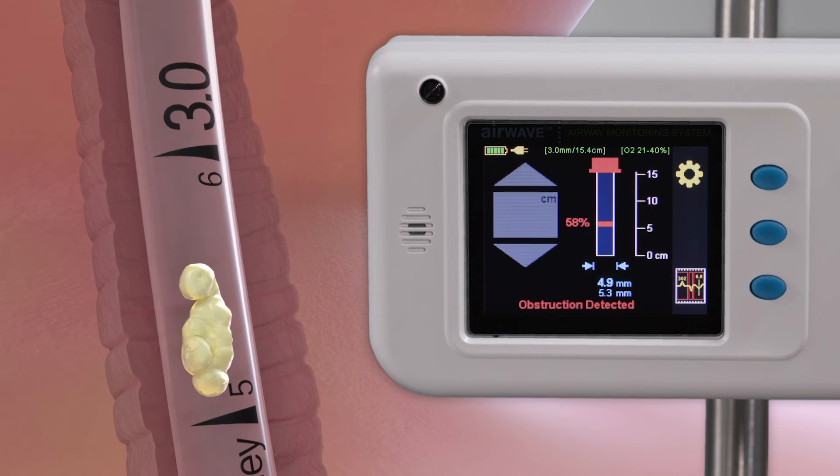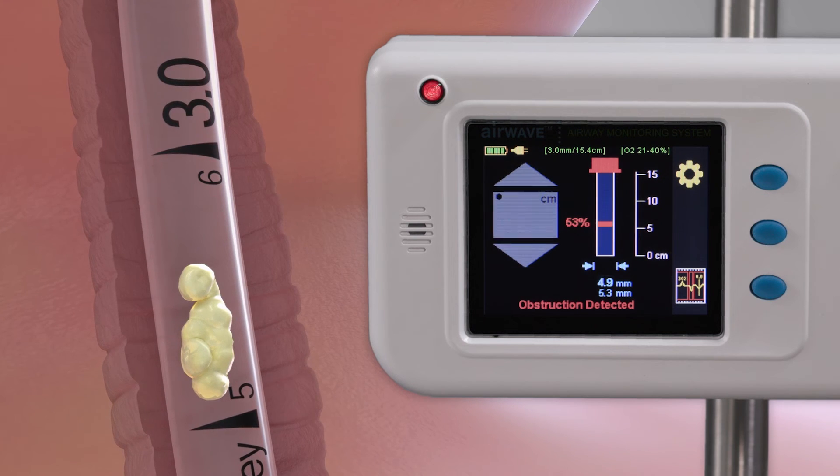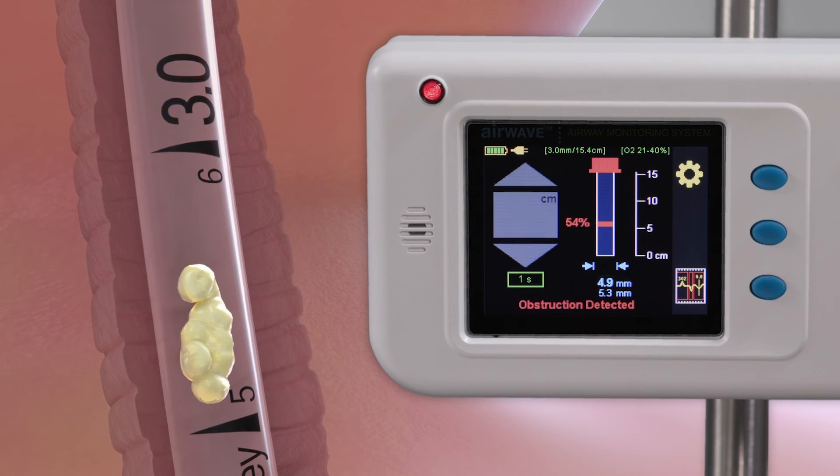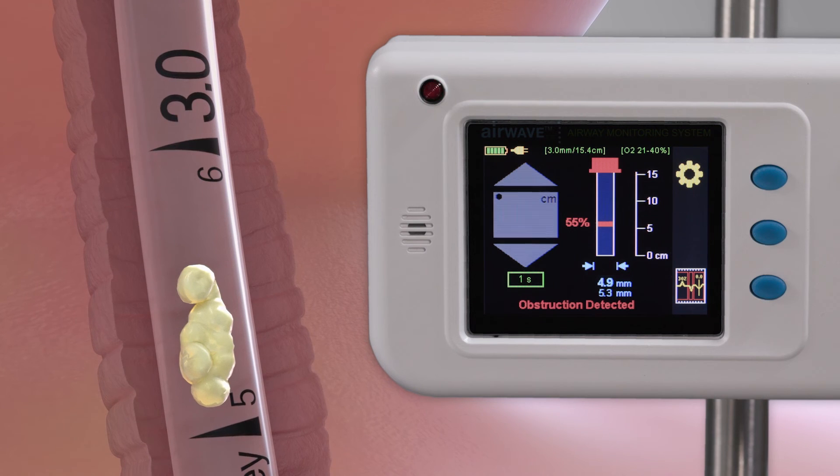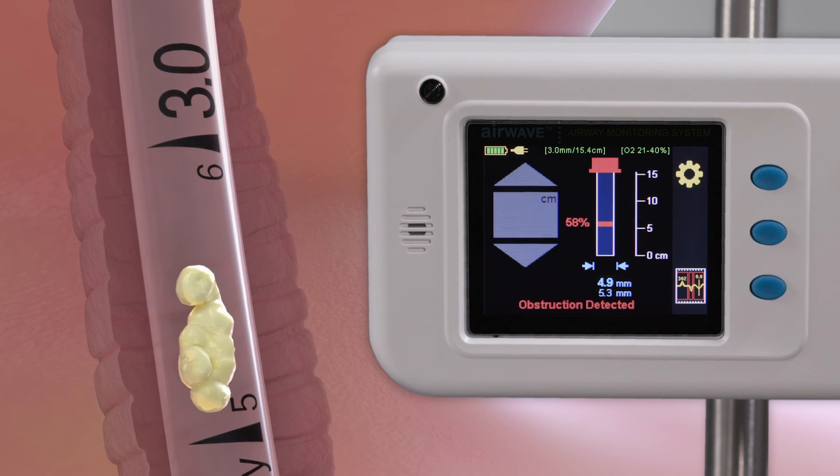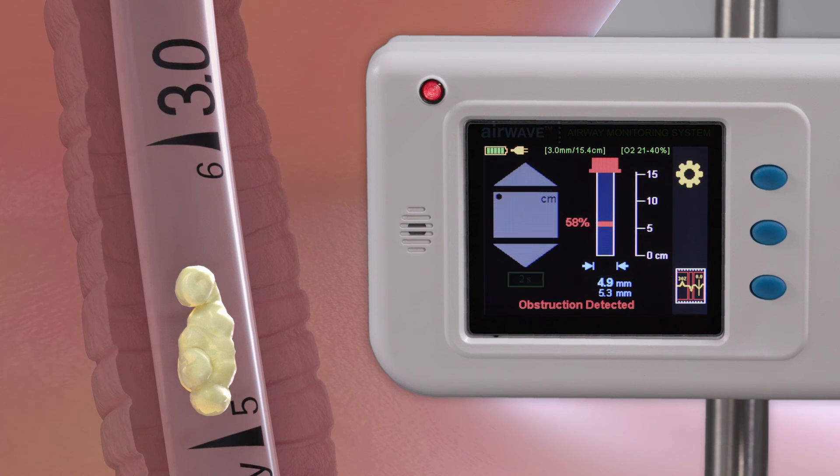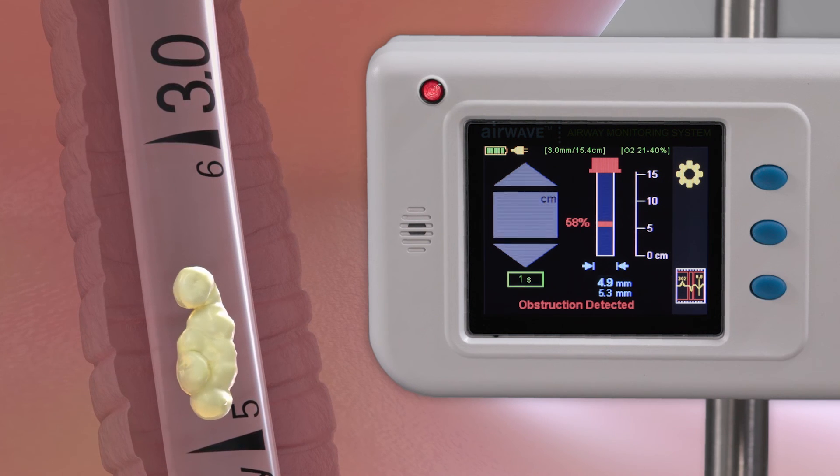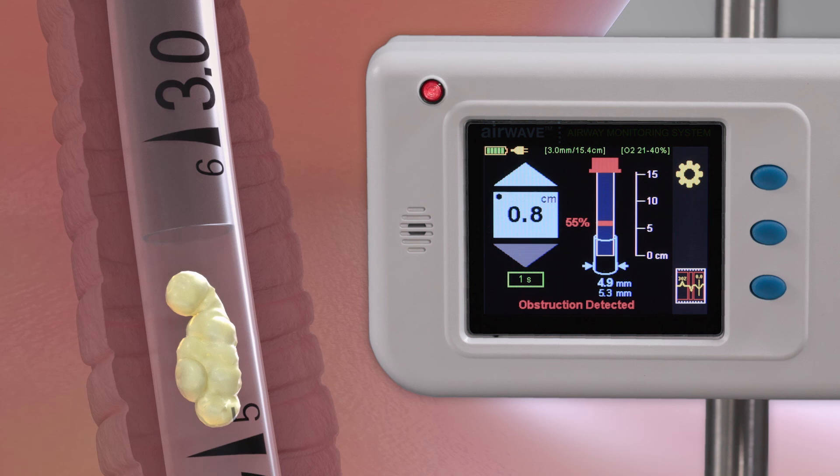When an obstruction is detected, the SonarMed device will display the location of the obstruction in relation to ETT depth markings. It will also indicate the percentage obstructed within the endotracheal tube, which may allow for more optimal suctioning practices.